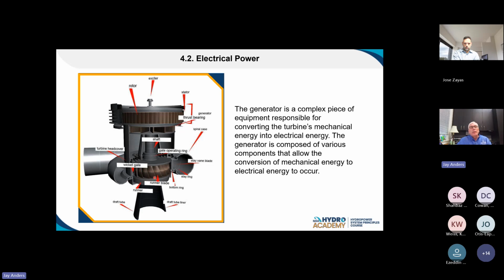Typically, hydro plants are not variably loaded devices. Either we pretty much load them up to their optimum point, or we keep them off. That goes back to something Jose mentioned earlier: if you operate your unit outside its normal bands of operation and you're not treating it the best that you should, that creates a lot of wear and tear. So, as I'm saying here, the governor is controlling the position of these wicket gates.